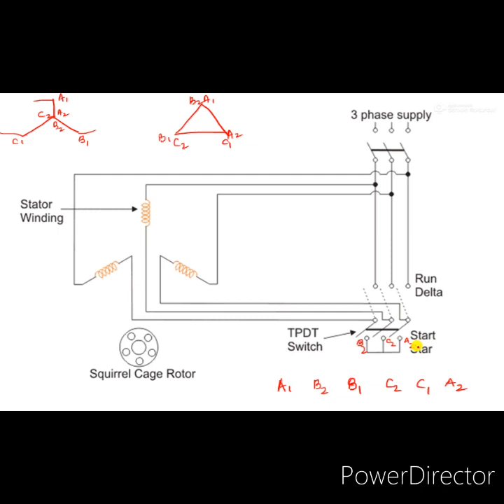In a star-delta starter, there is a TPDT switch — a triple pole double throw switch — operated with a handle that changes the starter from star connection to delta connection. This occurs once around 75 to 80% of the rated speed is reached. The rated speed is typically 1450 RPM or 1500 RPM. Once it reaches 75 to 80% of that value, we use the handle to change the position from star to delta connection, after which the running condition continues until we switch off the supply.